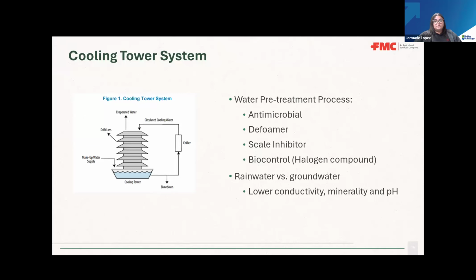As this evaporation occurs, it increases the concentration of dissolved solids that can form scale, and if it's not removed through a blowdown, this will cause operation problems. So the cool water is collected in the cold water basin at the bottom and is ready for reuse. But as the tower water level decreases, we need to add fresh makeup water to dilute the concentrated water. This makeup water is pre-treated with antimicrobial agents, defoamers, scale inhibitors, and other compounds to help maintain the water quality for the cooling tower operation.